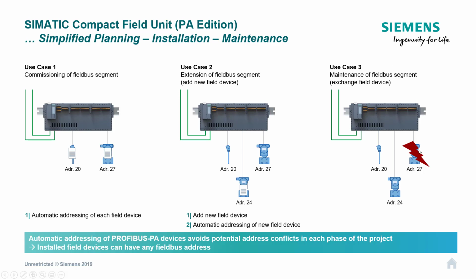So if you can get hold of manufacturer A, B or C quicker, as long as it's profile 3 or above, you can take that device out and replace it. It will automatically address, it will automatically switch over inside the device to the correct GSD profile. That's part of the Profibus PA standard, that it should do that. But just be wary, some devices and manufacturers try and force you to use their GSD, so you have to go into the parameter set and set it to look for a profile specific GSD. But anything above profile 3, can't say it enough, will work with generic GSDs.